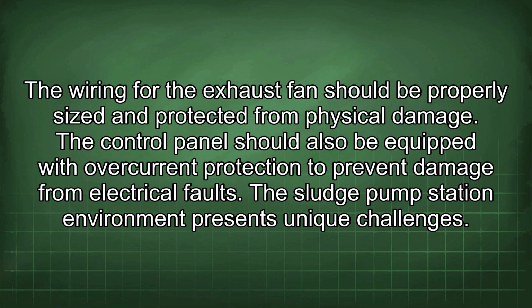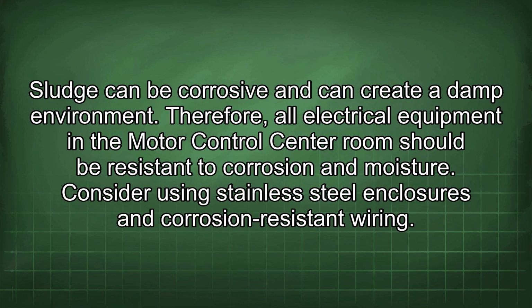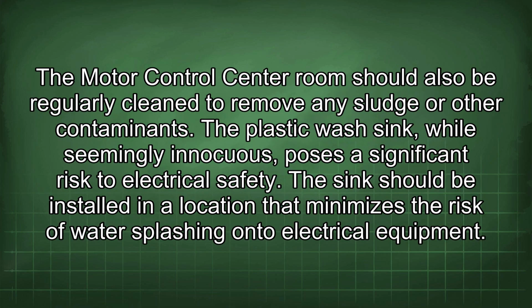The sludge pump station environment presents unique challenges. Sludge can be corrosive and can create a damp environment. Therefore, all electrical equipment in the motor control center room should be resistant to corrosion and moisture. Consider using stainless steel enclosures and corrosion-resistant wiring. The motor control center room should also be regularly cleaned to remove any sludge or other contaminants.